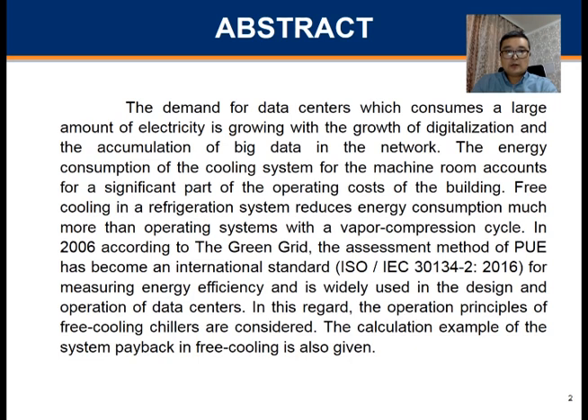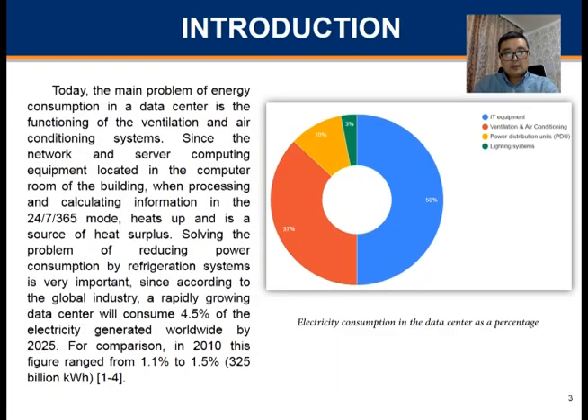The energy consumption of the cooling system for the machine room accounts for a significant part of the operating cost of the building. Free cooling in a refrigeration system reduces energy consumption much more than operating systems with a vapor compression cycle. Today, the main problem of energy consumption in a data center is the functioning of the ventilation and air conditioning systems.